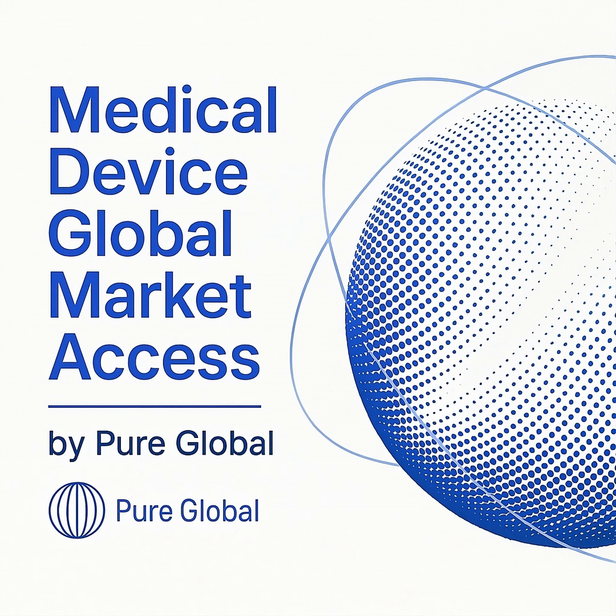Your MDR technical documentation provides a strong basis for the NMPA submission, but it cannot be used as is. The entire dossier must be restructured, translated into Mandarin, and submitted through the NMPA's Electronic Regulated Product Submission System. A key document you must create is the Product Technical Requirement, or PTR.